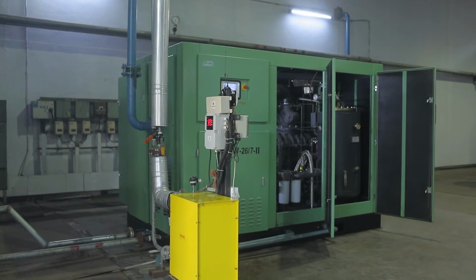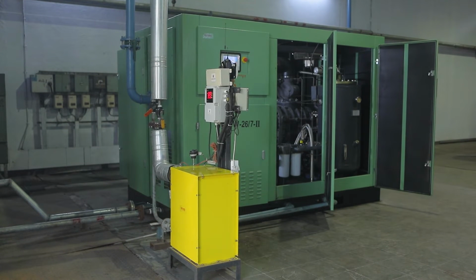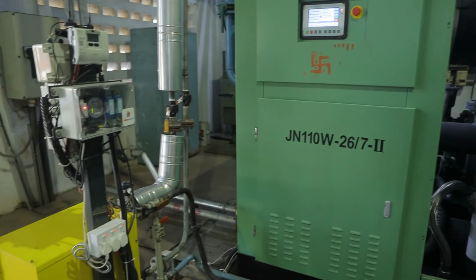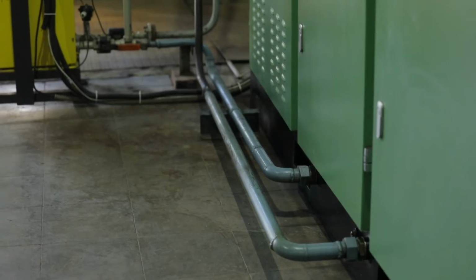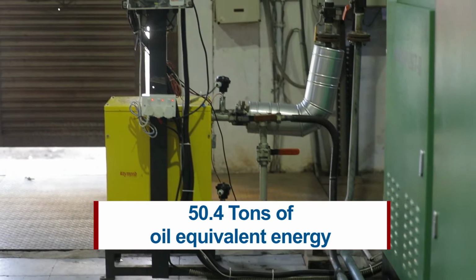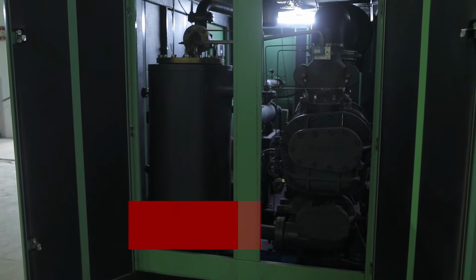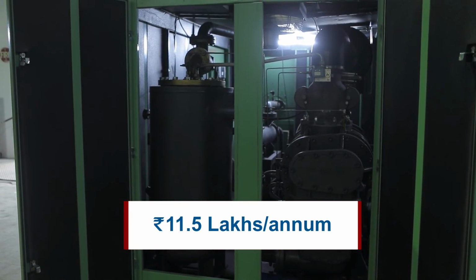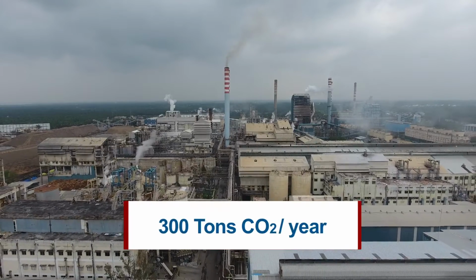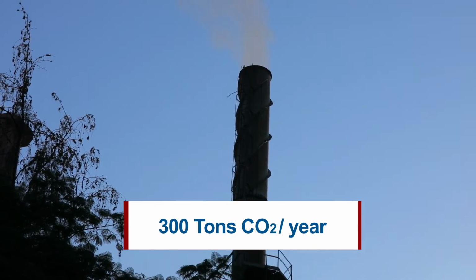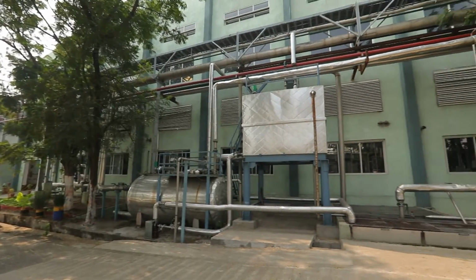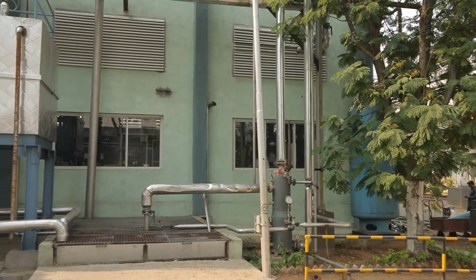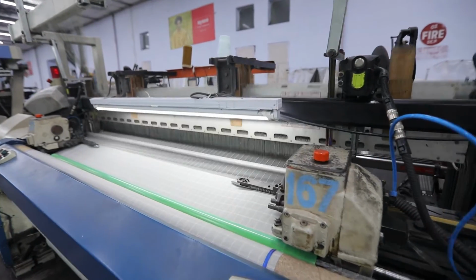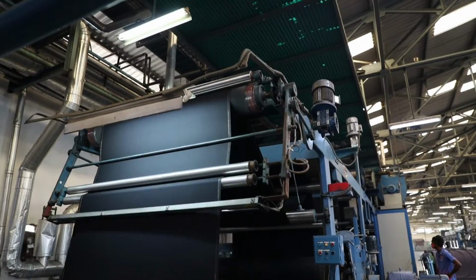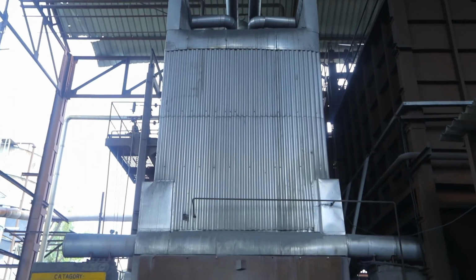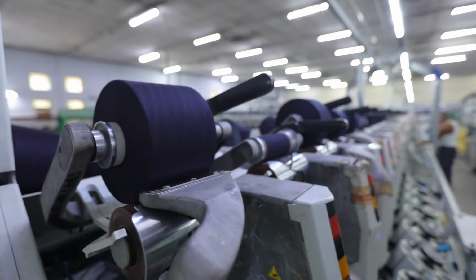Considering 930 CFM compressor running at 95% load on an annual basis, the installation of waste heat recovery system will lead to an annual saving of 50.4 tons of oil equivalent energy. It will lead to a monetary saving of Rs 11.5 lakhs per annum. It will result in greenhouse gas emission reduction of 300 tons CO2 per year. The air compression is used across various processes in the textile industry like pneumatic supply for instrument air, air looms in weaving, air padding in dyeing, ash handling system in boiler house, and different machines of spinning and combing.